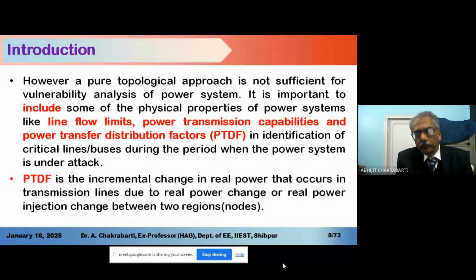These terms are incorporated from the topological approach, but when applied to power systems, we need to include physical properties and constraints like line flow limit, power transmission capability, and PTDF - power transfer distribution factor. PTDF plays a very important role in contingency analysis, as you all know. It is used so we can model the system during contingency effectively. Let me recall the concept of PTDF. It is basically an incremental change in active power, the real power, occurring in a transmission line due to real power change or injection change between two regions.